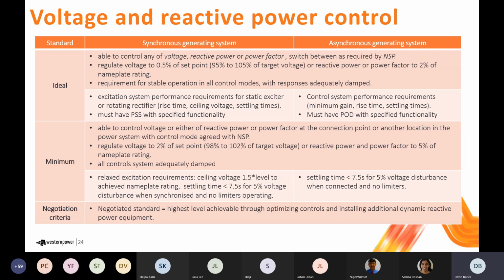You also need to make sure that your control systems are operating stably in all control modes. And depending on the technology employed, you'll need to meet certain performance requirements. The requirements for synchronous generating systems are your typical excitation system performance requirements: ceiling voltages, rise times, settling times and the like, and the need for a power system stabilizer. The requirements for asynchronous generating units have been expressed more in terms of control system parameters: minimum gains, rise times, settling times, and the need for a power oscillation damper to be fitted. So that's the requirements for your large generating system to meet the ideal standards.